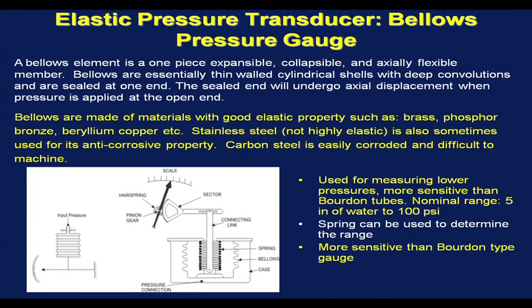Let us continue with our discussion on elastic pressure transducers. In our previous class, we talked about Bourdon gauges. Today, let us talk about the next elastic pressure transducer, the bellows pressure gauge. A bellows element is a one-piece expansible, collapsible and axially flexible member. Bellows are essentially thin-walled cylindrical shells with deep convolutions and are sealed at one end. The sealed end will undergo axial displacement when pressure is applied at the open end.